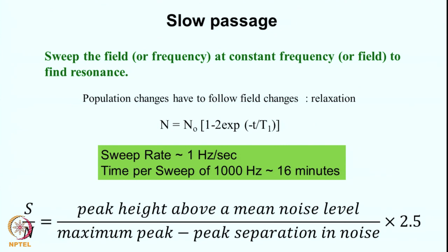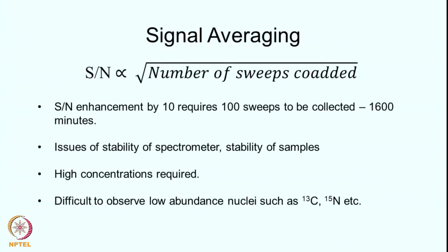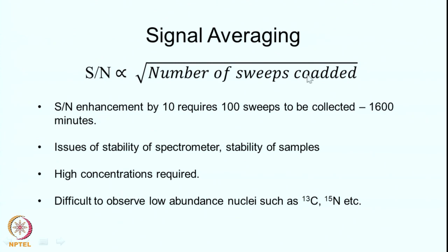To increase the signal-to-noise ratio, you can use signal averaging — sweep the spectrum several times and add them together. The signal adds as the number of scans, whereas the noise adds by the square root of the number of scans. Therefore the signal-to-noise ratio goes as the square root of the number of sweeps co-added. To enhance signal-to-noise by a factor of 10, you need 100 sweeps — at 16 minutes per scan, that is 1600 minutes.